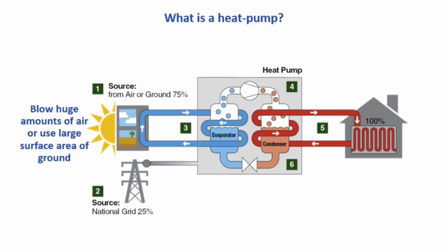The temperature raised up to, say, 50 degrees, we transfer heat into this second loop. This system loop could be similar to what you'd experience in a normal gas system boiler. It's just a lower temperature typically. Once the condenser is settled and at pressure, it then enters an expansion valve, which allows the refrigerant to escape and depressurize into the evaporator.